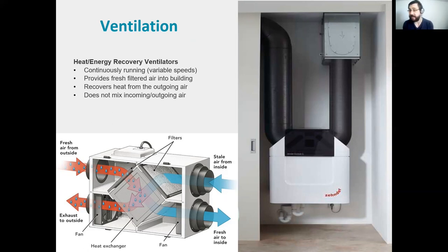Then it goes into a heat exchanger. This heat exchanger takes some energy from the outgoing air, the air being pulled from inside the building that's warmed in winter, and passes that through the heat exchanger as well. The air isn't mixing, but it's taking some of the heat energy from the outgoing air and transferring it to the incoming air, pre-warming it, then putting that pre-warmed air back into the building.